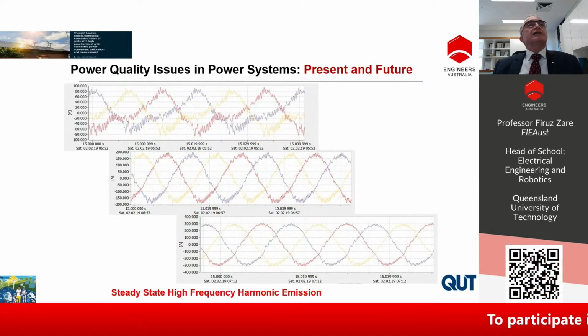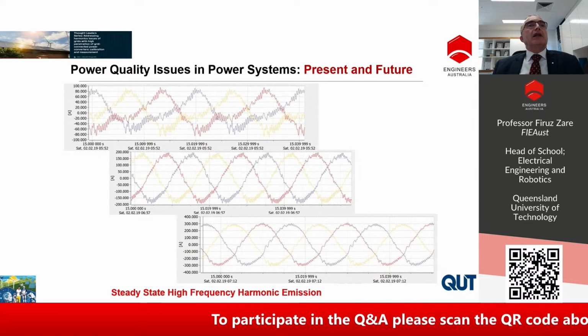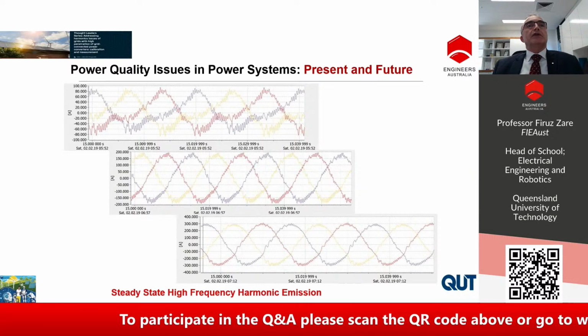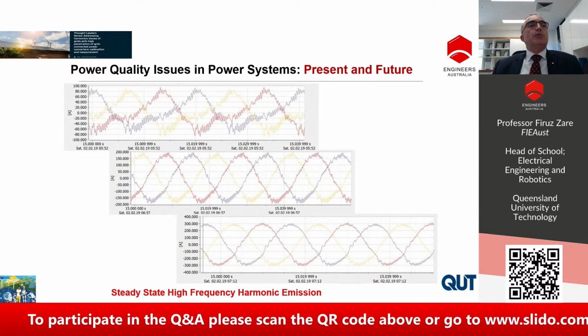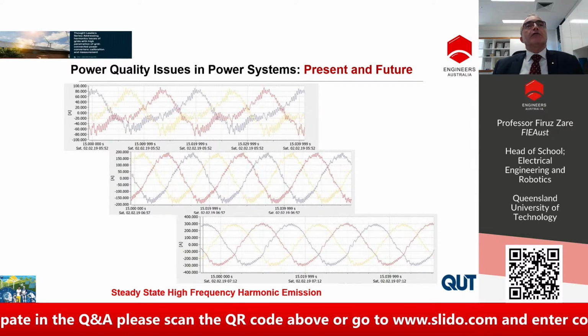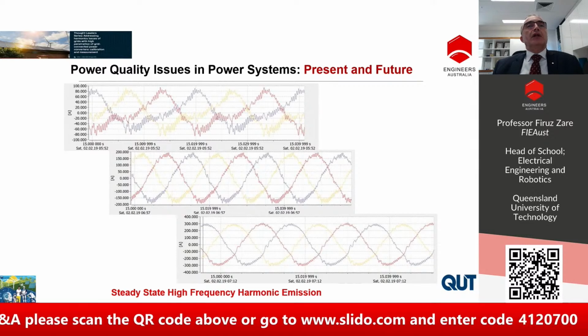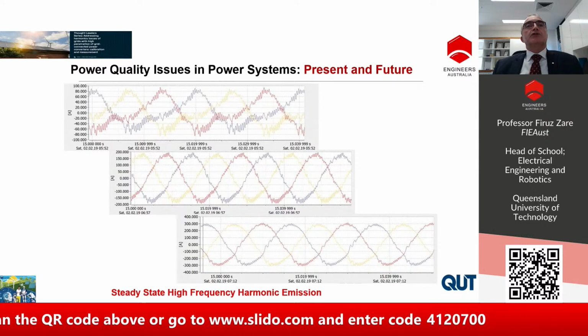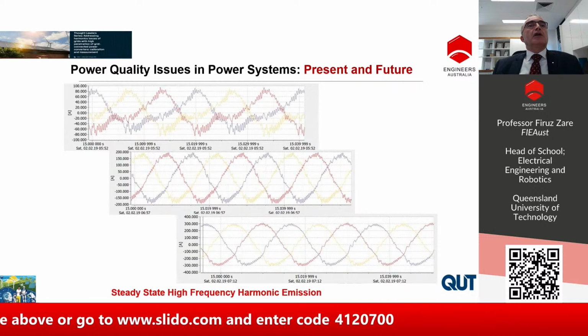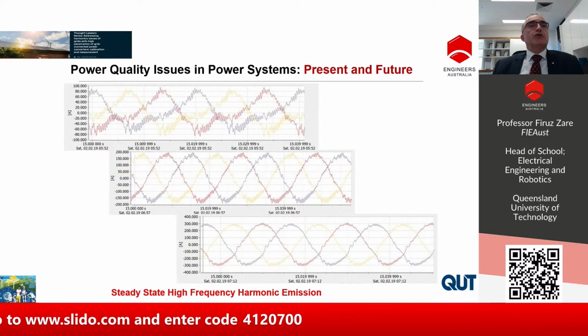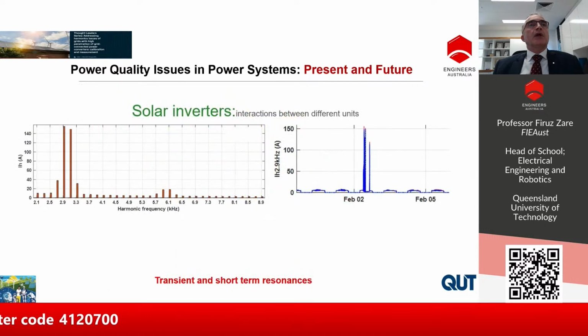So this is another example of power quality measurement that we did in Australia. You see that the grid-connected solar inverter should have a more or less perfect sinusoidal current waveform, but depending on the different operating modes, the current is not purely sinusoidal. It has significant harmonics in the network.